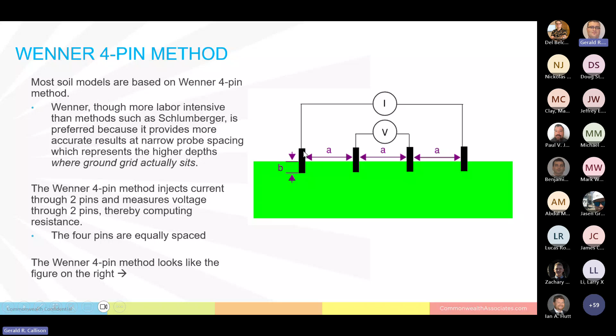So this shows that equation 49 does provide some additional accuracy, and we'll talk a little bit more about that in future slides. Now, we've got all these little resistance numbers at differing spacings, because you're going to specify these over a horizontal trace. You're going to specify increasing A distances, maybe 2, 4, 6, 8, 10 feet, 20, 30, 50, up to 100 by 10s, then 100, 200, 300. Then you're going to get these resistances at differing A spacings, and you have to put them into grounding software to create an actual model of your soil.